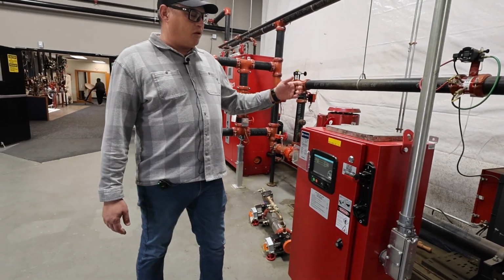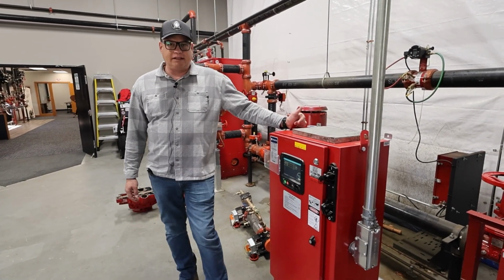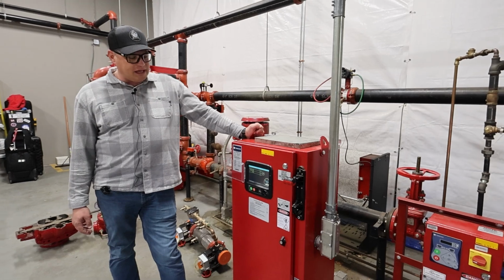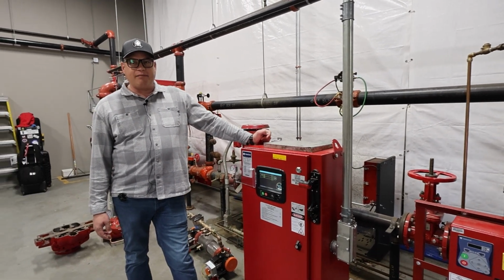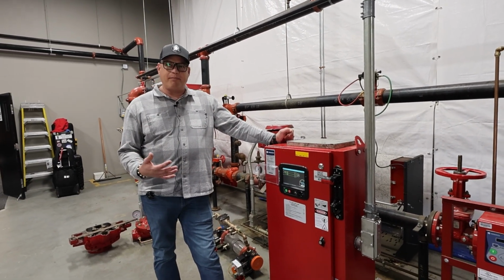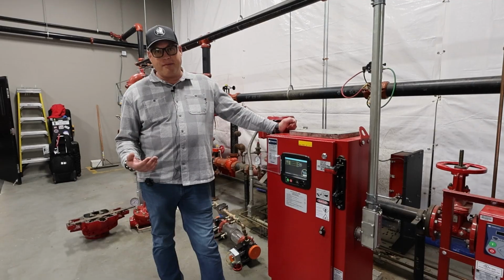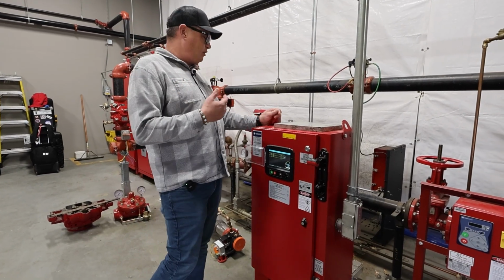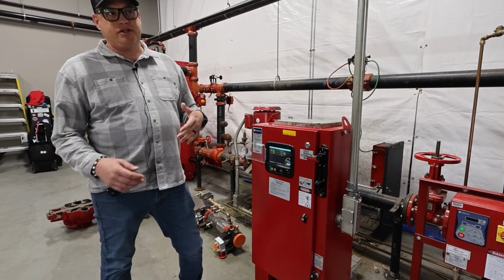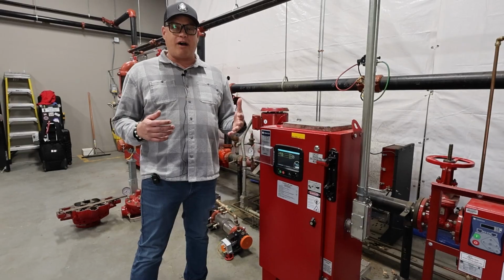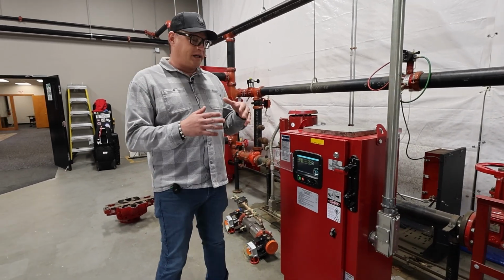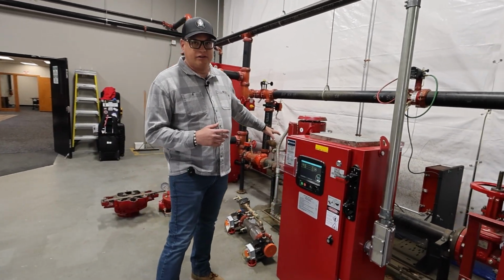But also, it's only 30 minutes for a diesel and 10 for electric. It's not a whole lot of time, but it gives you time to check things like temperature of the fire pump, speed of the fire pump. You're also measuring your suction and discharge to ensure that your closed valve pressure, your shutoff, is what it's supposed to be per the records of that fire pump.